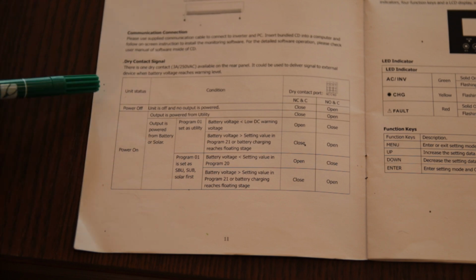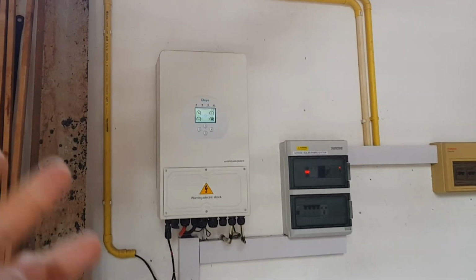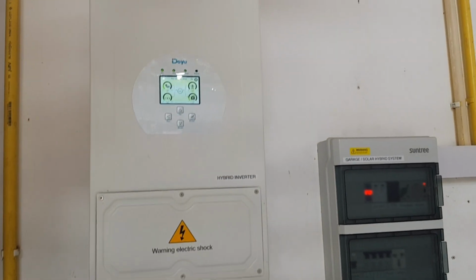If the inverter is powering off by some fault or even losing power completely, then typically that contact could go into a different state, into the opposite one from what we need. But such cases are extremely rare. In my situation here on my all-in-one inverter, I actually never had a downtime of the inverter where it went out of the mode. Yeah, so better than the all-in-one inverters is of course something like this here.